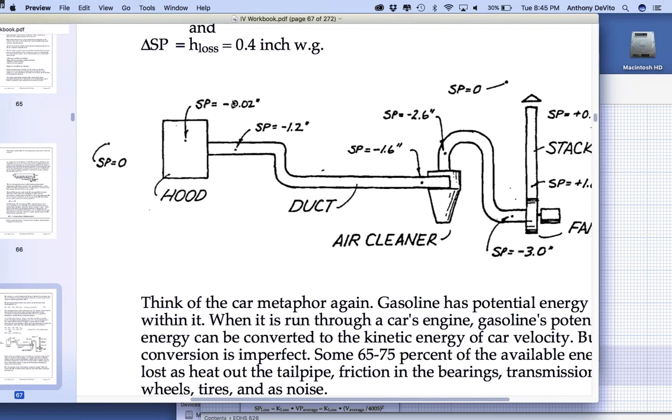Okay, so the static pressure inside the hood is not very big, but there's a point here, static pressure, which is just inside the hood, certain size duct. At a certain point, a certain number of diameters of ductwork up from the hood, they measured a static pressure of negative 1.2 inches. When we design these systems, we're going to choose, this is the hood we need for this job. ACGIH and some organizations and the manufacturers, they have technical specs on hoods. And they'll tell you to capture at this distance, this kind of particle, this kind of fume, and so on and so forth, that at this point here, you need a certain static pressure if you connect the duct to it.